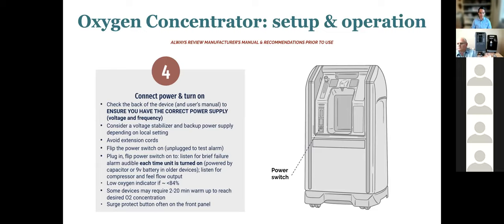So when we have the unit and we're getting ready to plug it in, before you plug it in, you can flip on the power switch and test to make sure that its failure alarm is working. If it is, the oxygen concentrator, even though it's not plugged into the wall, should sound an alarm to let you know it's not plugged into a wall. So you can test that out before you start using it. Once you've done that, you can plug it into the wall.